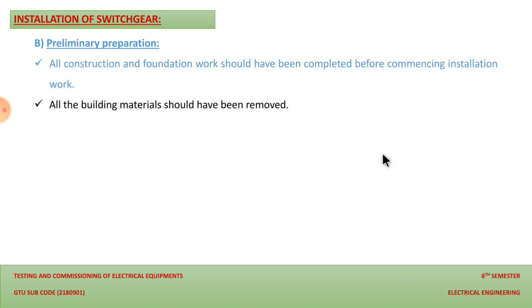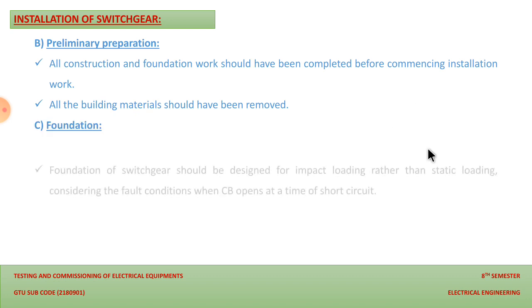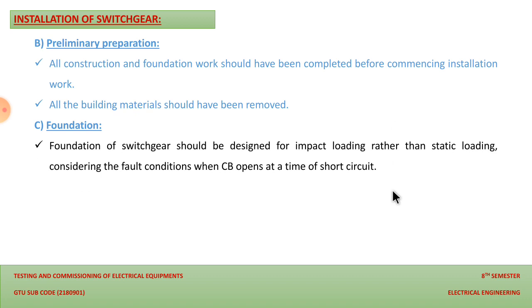Then all the building material should have been removed. So yes, as we have done the civil work, cementing and other things like sand and water are there, so we have to remove all those things to protect our device from getting contaminated. Then the next point is foundation. The foundation of the switchgear should be designed for impact loading, rather than static loading, because when the circuit breaker operates, there will be vibration. So considering the fault condition, when the circuit breaker opens at the time of a short circuit, we have to design the foundation according to the operation and size of the switchgear, so that it becomes viable for future protection purposes.